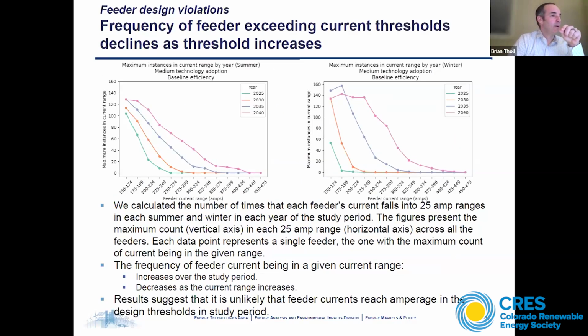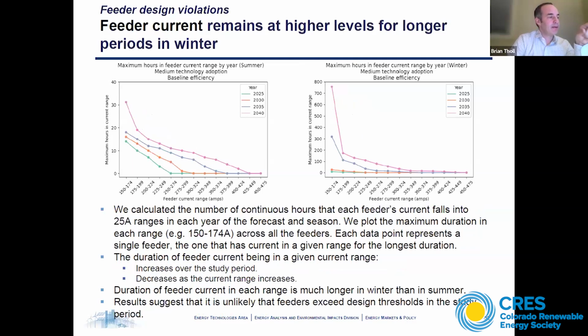Certain duration. In the results, these are instances - we're not necessarily seeing that in the model. We're not seeing the amperage go up at the feeder level to reach that total amps that might risk that. And then this result is the duration - how long did we see the cable supporting that amperage in the model? We see it's far below the time needed to result in a thermal overload for the infrastructure.